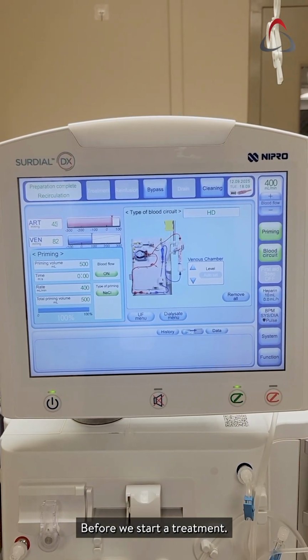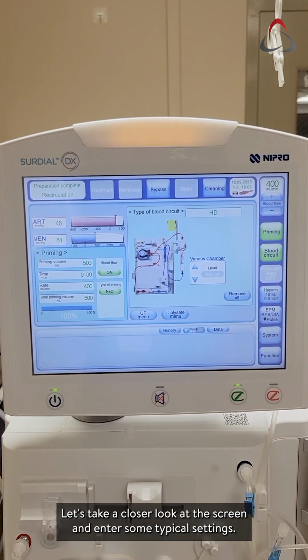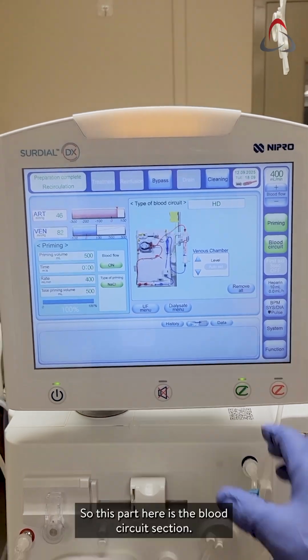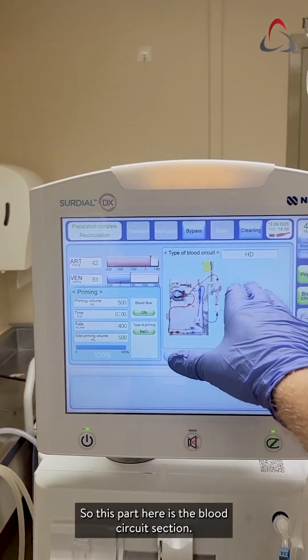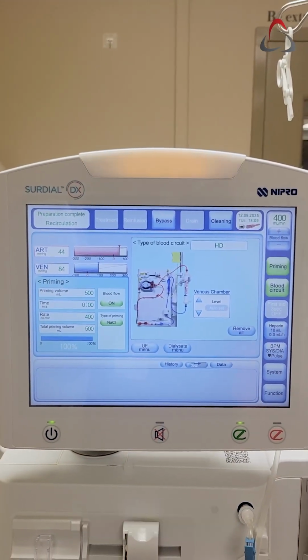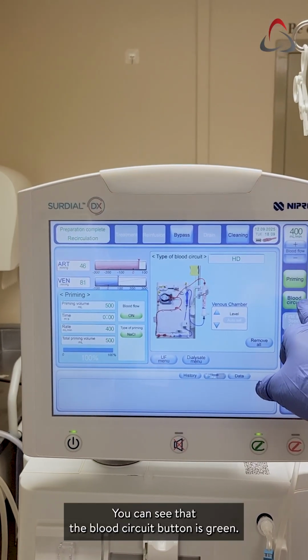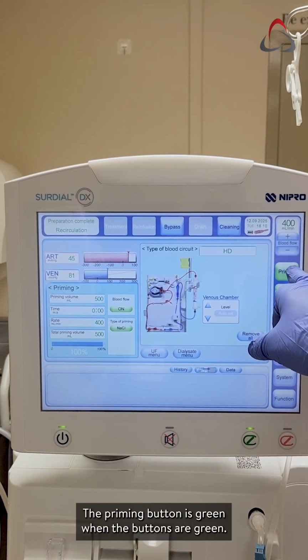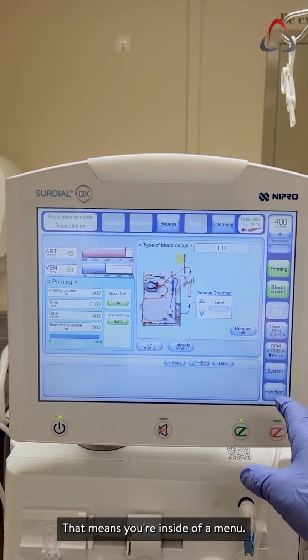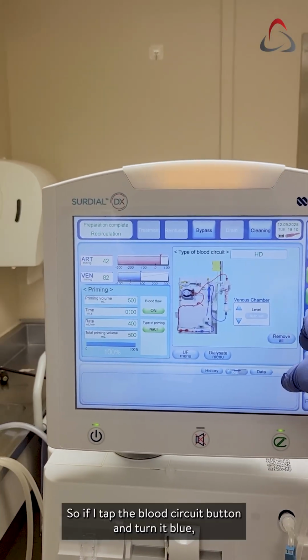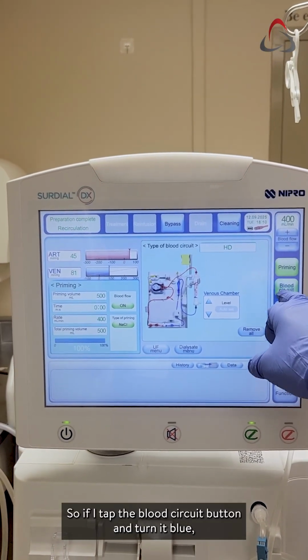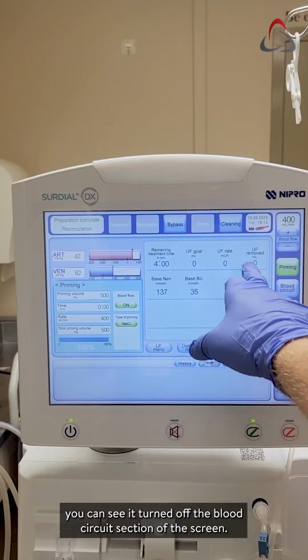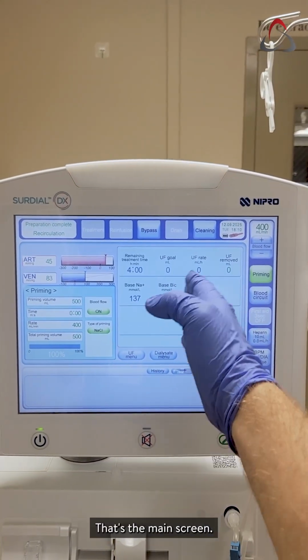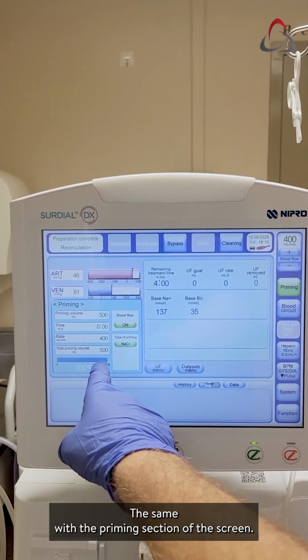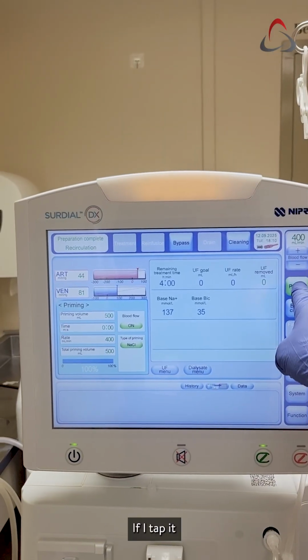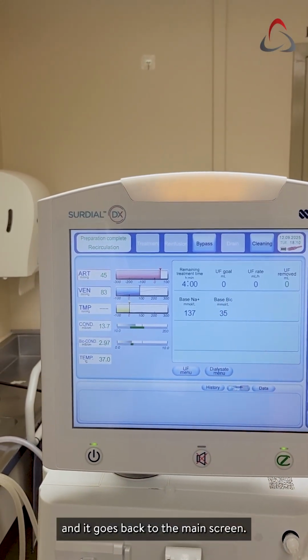Before we start a treatment, let's take a closer look at the screen and enter some typical settings. So this part here is the blood circuit section. You can see that the blood circuit button is green. The priming button is green. When the buttons are green, that means you're inside of a menu. So if I tap the blood circuit button and turn it blue, you can see it turned off the blood circuit section of the screen. That's the main screen. The same with the priming section of the screen. If I tap it, it goes back to the main screen.